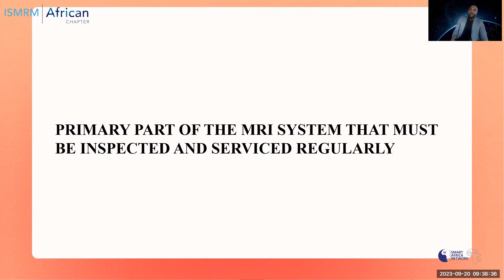Parts of the MRI system that must be inspected and serviced regularly. As a biomedical engineer, I focus majorly on preventive maintenance of this MRI system, and the cold head becomes very important to me, and also the cooling system. Knowing that the cold head works 24 hours, the need to maintain this cold head is paramount. In doing this, during the preventive maintenance phases, the cold head and the cooling system are checked to ensure that they are all functioning well. Also, the cooling water from the primary to the secondary water pump is checked to ensure that the water is in good gauge.